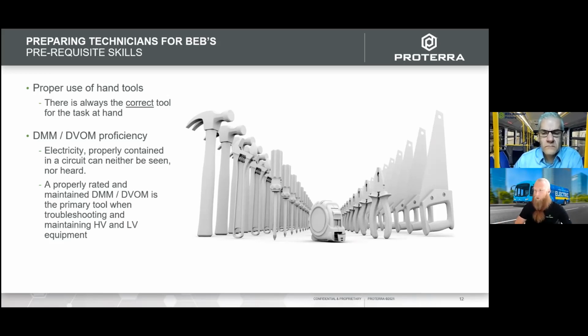It's also important to point out that you should not rely on voltage tester pens, at least on BEBs, because the majority of everything you're working on is actually DC voltage, so it's not the proper tool to test for voltage. Even further, the AC voltage on this bus—most of those tester pens are not rated for it. So even if we're looking at an AC voltage of 230, most tester pens are only rated for about 120. It poses a safety risk.